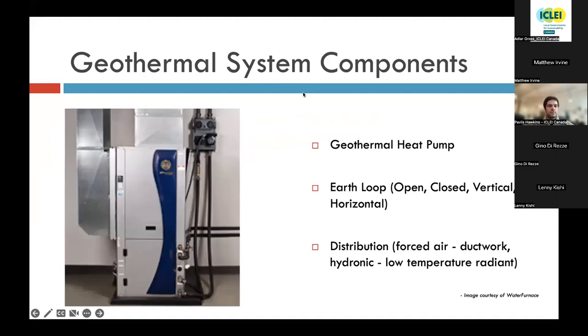So the geothermal system components are the geothermal heat pump, seen in that picture to the left, the gray box with the blue decorative on the front, the earth loop, which can be open or closed, a closed vertical or closed horizontal. The only earth loop portion you see in this picture is in the upper right-hand corner. You'll see the flow center with pipes connected. That's circulating the fluid from the earth loop to the heat pump. And then, of course, you're going to have your distribution system, whether that's forced air with conventional ductwork or hydronics, such as in-floor radiant or low temperature radiant panels on the wall or elsewhere in the house.